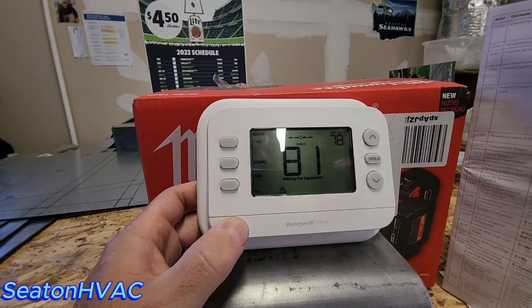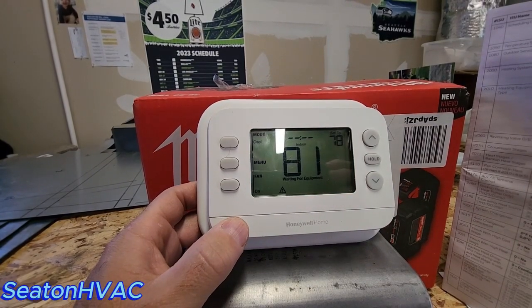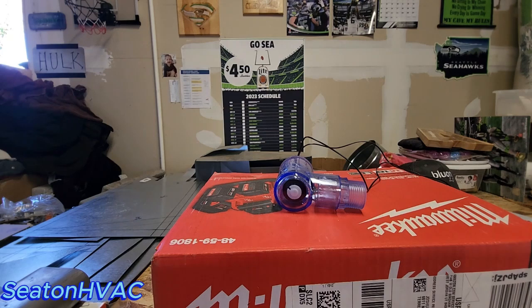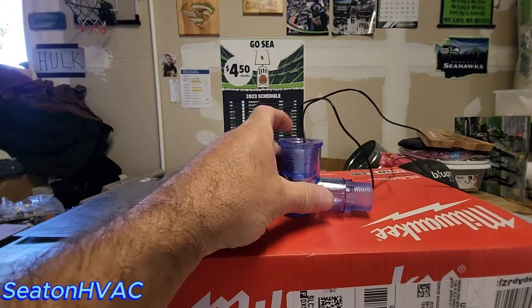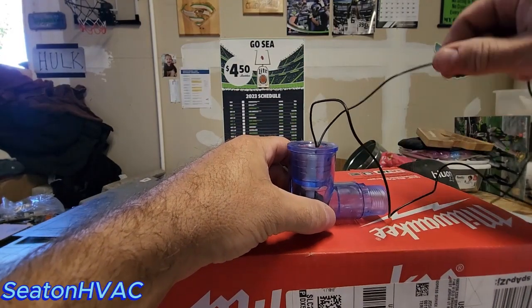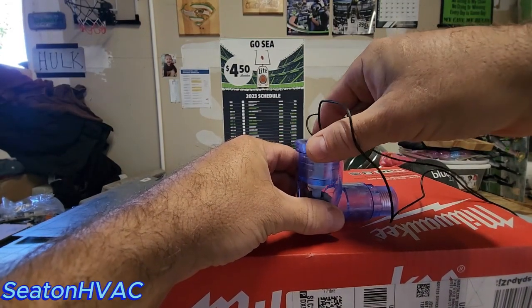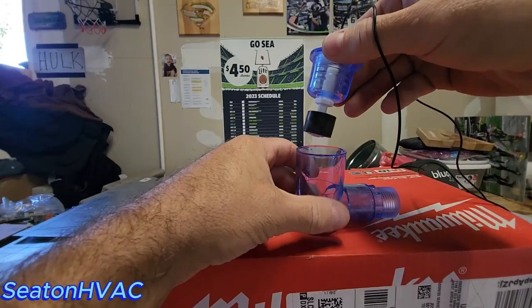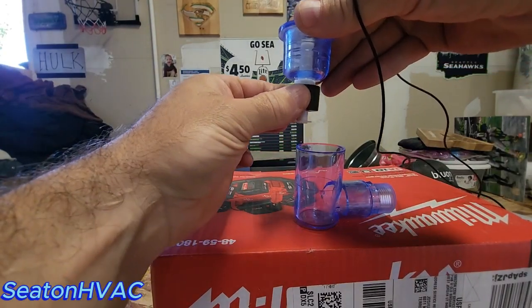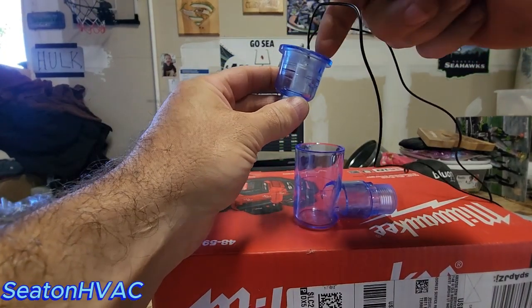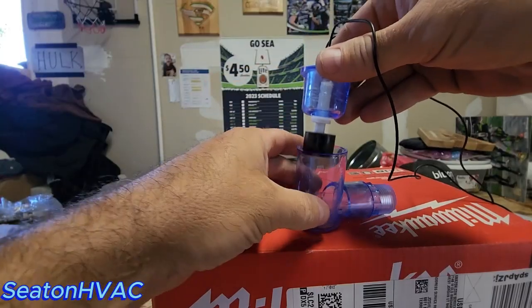Last thing we're going to do is that float switch, and then I'll conclude the video. All right guys, simple float switch. I won't waste too much time on this because it's a basic thing. So it's got 2 wires. All this is doing is breaking your circuit if this pops up, okay? So it's got this little float in it. If this guy goes up, all of a sudden this is open. Your power's in, but your power's not coming out. It'll kill your equipment. That's all it is.